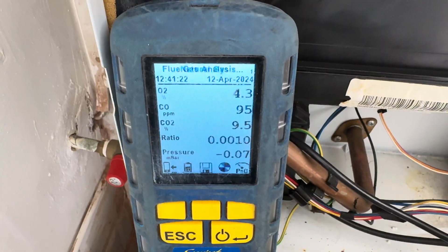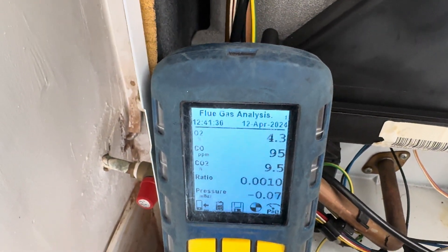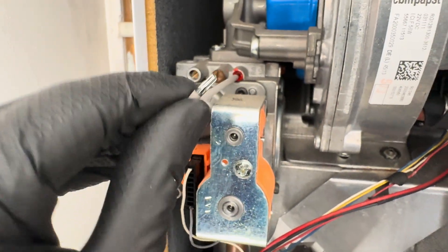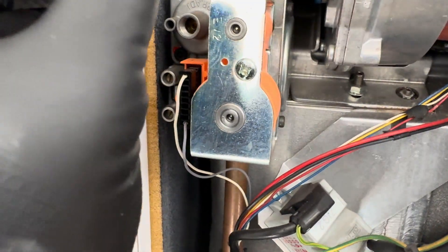So this is what we're getting in high flame, which is fine. We might lower that a little bit just to get a slightly better reading. It's really difficult to do this - it's clockwise to decrease. I had to use a star T10 for this because the paint is a nightmare on there.